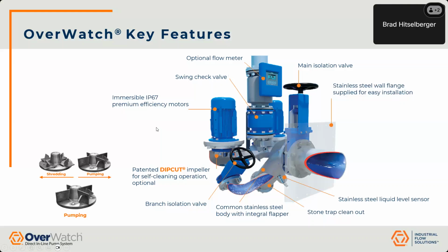So normal operating modes, we usually have this. We size it for full redundancy. One side does all the peak capacity that it can handle and the pressure points that it can handle. If it needs to go into reverse, all the impellers can go forward or reverse. And then the other operating mode it can go in is it will run in a parallel condition if one pump cannot keep up, basically.